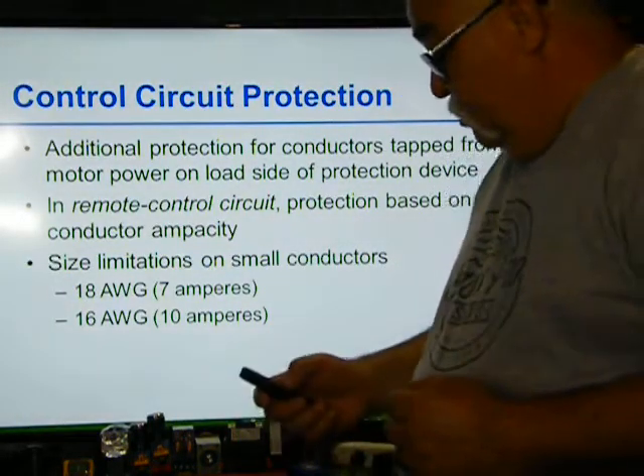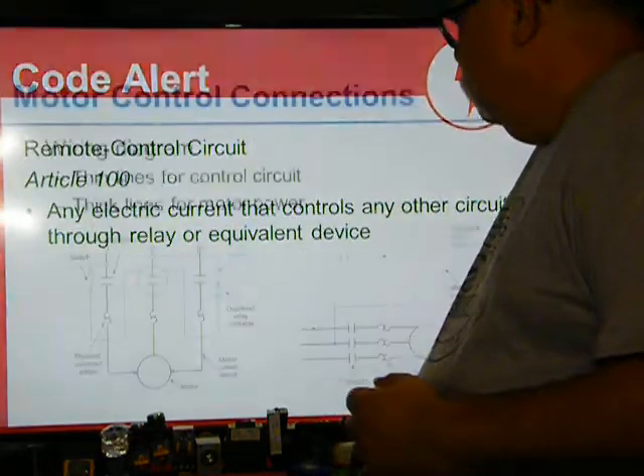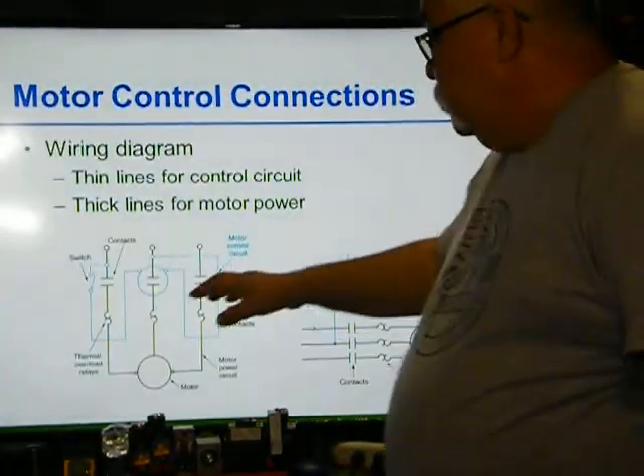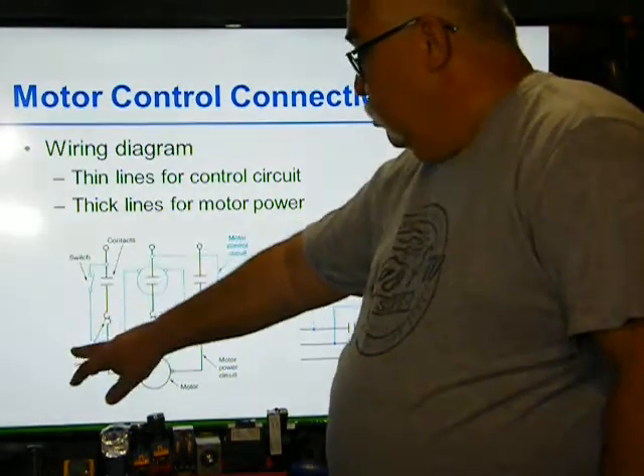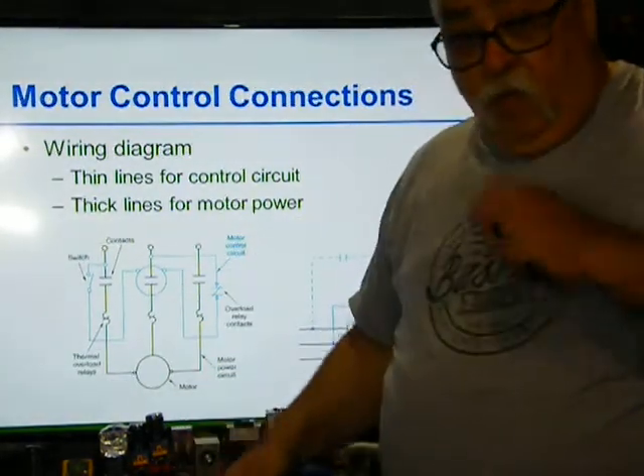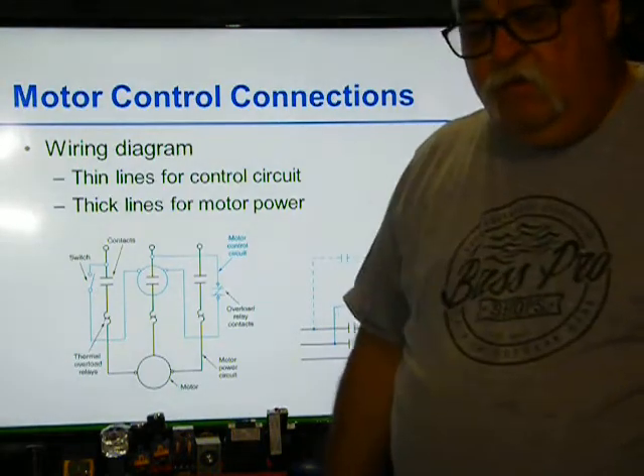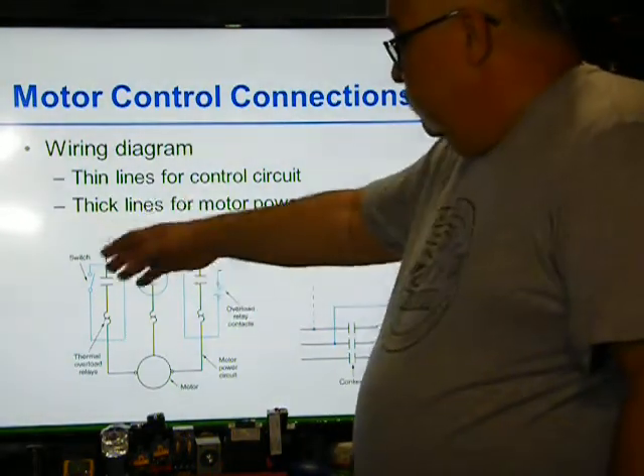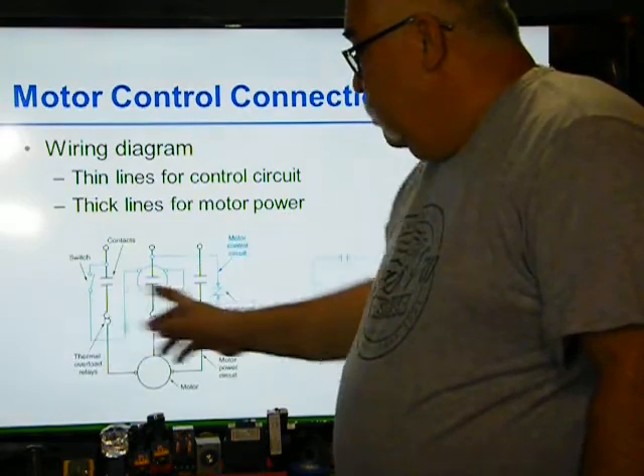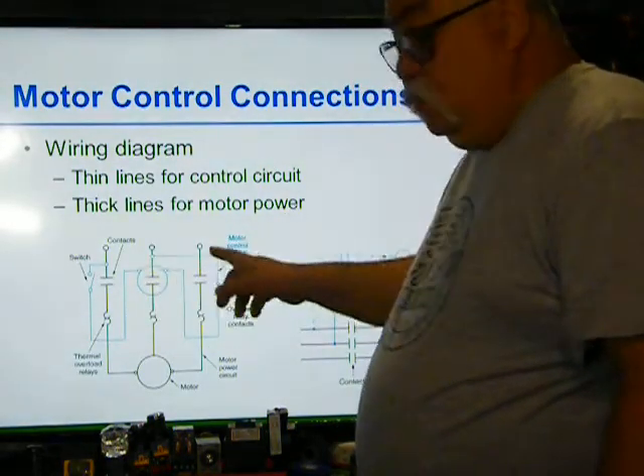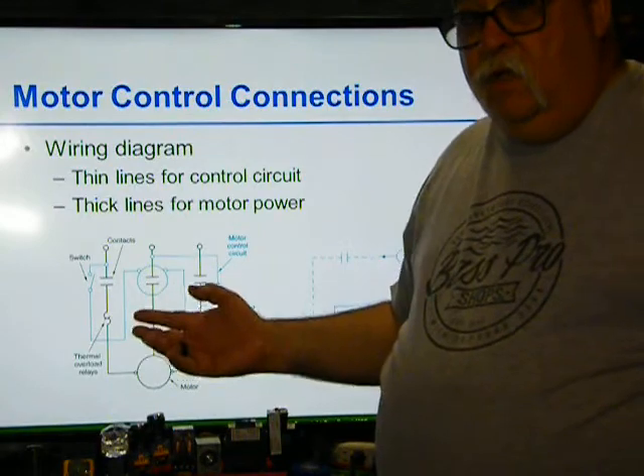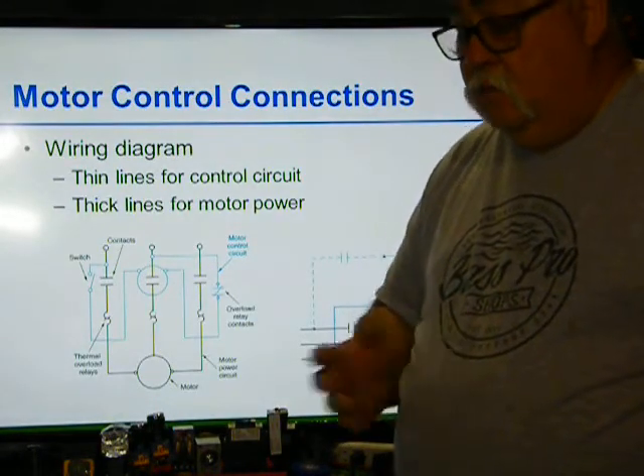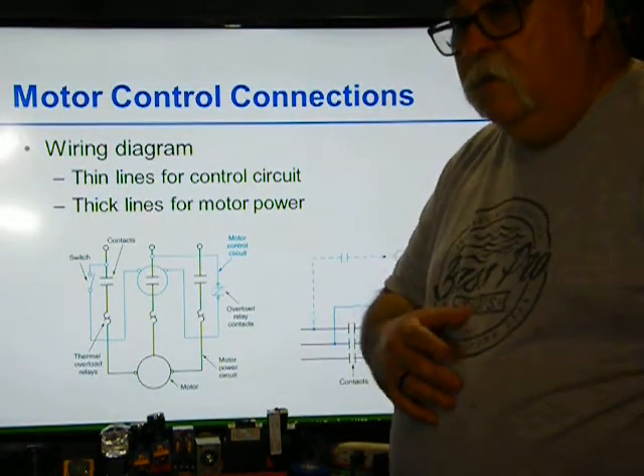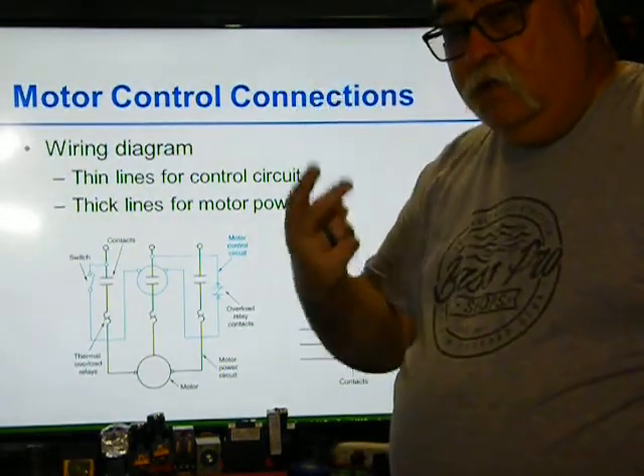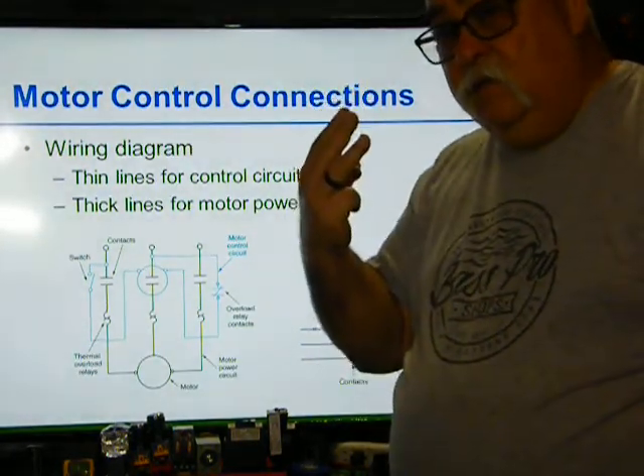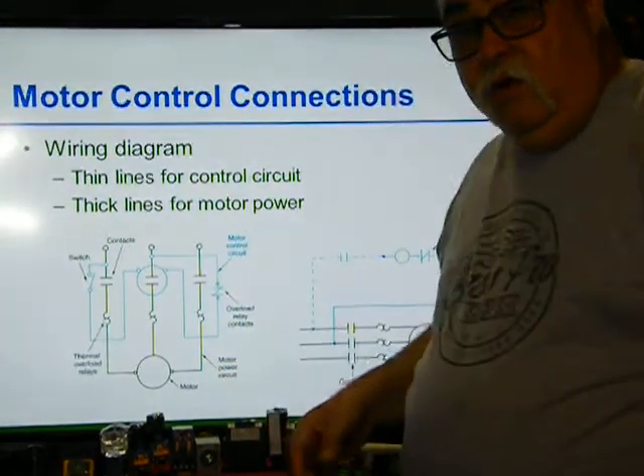A lot of times what we do is, let me get back to this drawing. When we come off these drawings, we'll go to a transformer. Let's say we've got 480 coming in, or even 208 or 230, 240, and I'm getting 2 hots because there's no neutral. A motor does not need a neutral unless it's 120 volts. For the most part, a single-phase motor has 2 hots, and a 3-phase motor has 3 hots. No neutral. You don't see a neutral anywhere on there.